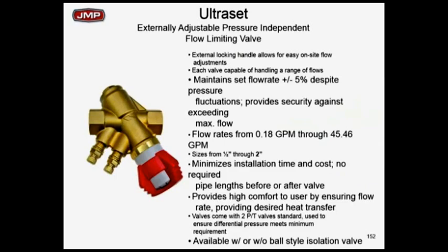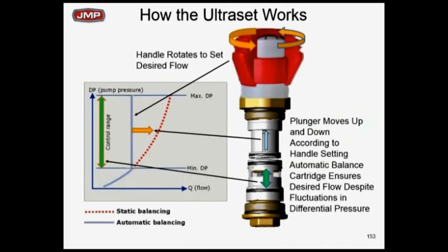It's plus or minus 5% accuracy, and you've got full stroke available to you. Great concept. So the point of a pressure independent control valve is to make sure you limit the flow and you keep the delta T up at partial loads. That's the advantage of a pressure independent control valve.